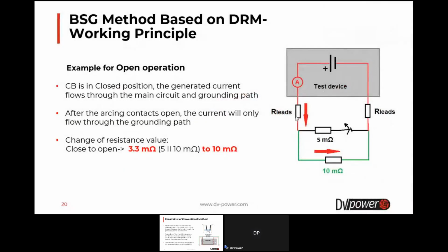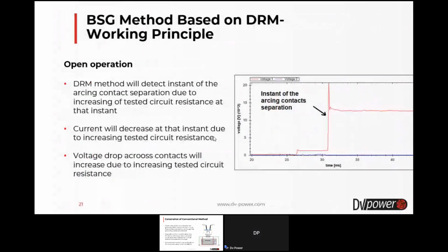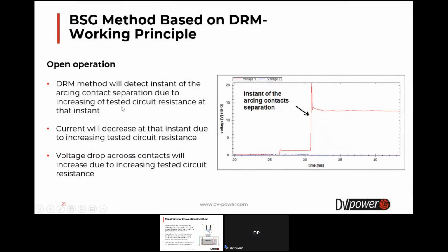Regarding the open operation, we start from the closed position, and the generated current flows through the main circuit and the grounding path. The value of the resistance of this equivalent circuit is 3.3 milliohms. At the moment when the arcing contact opens, the resistance changes from 3.3 milliohms to 10 milliohms, because when the circuit breaker is open, the test device sees only the resistance of the grounding path. So the dynamic resistance method will detect the instant of the arcing contact separation due to the increase of the tested circuit resistance at that instant, as you can see from this diagram. Current will decrease at that instant due to the increased tested circuit resistance, but voltage drop across contacts will increase due to the increased tested circuit resistance.